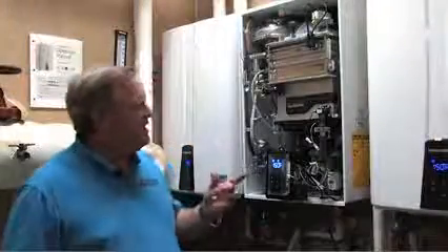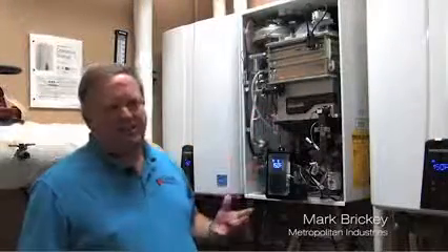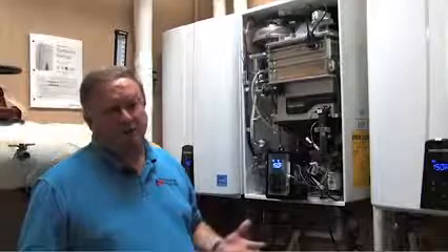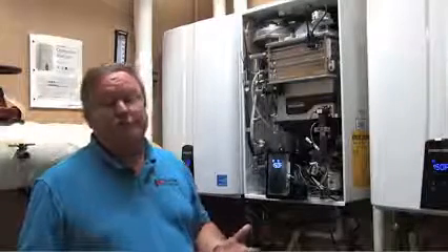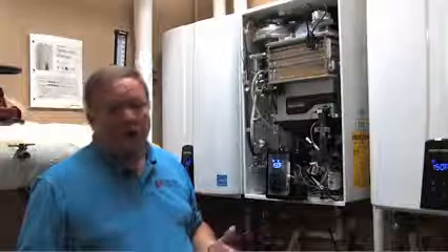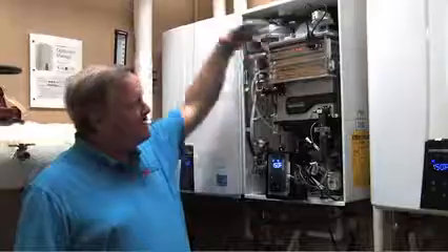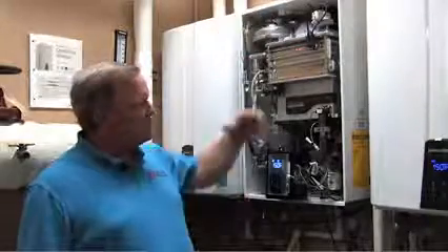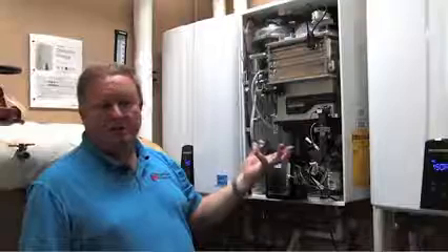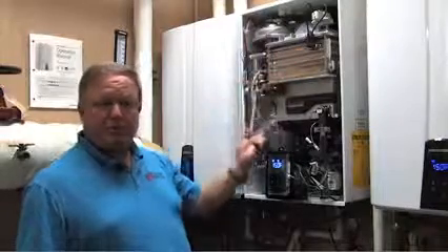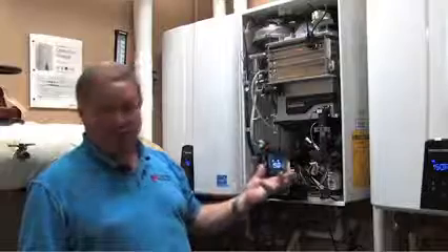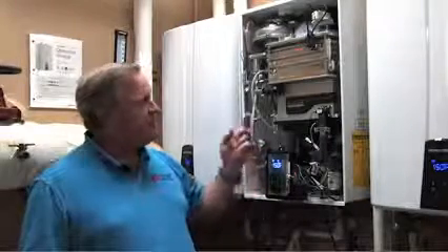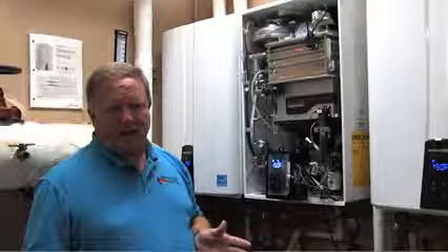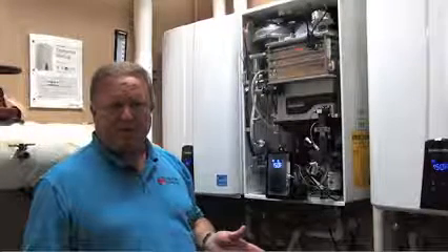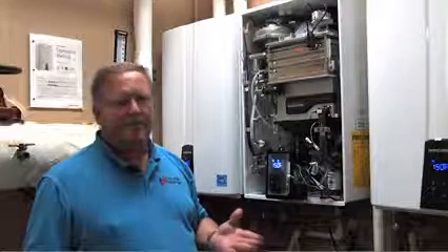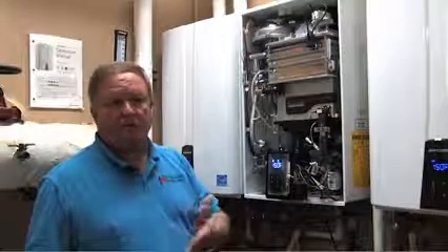The advantages of the stainless steel heat exchangers are that being stainless steel, the minerals that are in the water don't adhere to it as much as it would if they were copper or aluminum. So you don't have to clean them out as often. This is a top-down burner. The burner's up top, and so you get less debris than you would if you had the burner down below. Any debris that didn't burn completely would fall on a burner if it was a bottom-up burner. Another thing is that these do not burn as hot as some other manufacturers do. Ours is much lower temperature, so we don't bake the minerals out of the water as most of our competitors do.